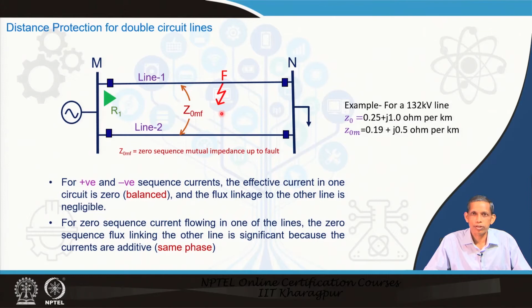So, this says that the 0 sequence current has a mutual impedance with the other circuit, whereas the other sequence components, positive and negative, do not have such impedances; they are negligible. So, this leads to our analysis for the double circuit line being a little bit different from what we derived for the apparent impedance calculation for the single circuit analysis.